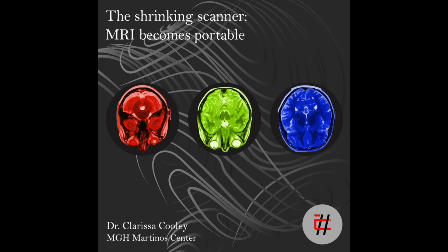I think that a really important aspect of our approach was, we tried to think outside the box instead of just thinking about scaling down a conventional MRI scanner architecture. We tried to reimagine the way that MRI is done. And so this started really with the magnet design. Instead of using a large full body superconducting magnet, we used a small permanent magnet array that fits around the head only and is specialized for head imaging, brain imaging only. So it reduces the applications to a specialized application space. But it allows us to really produce this very portable design to bring MRI to places where it was not available before.